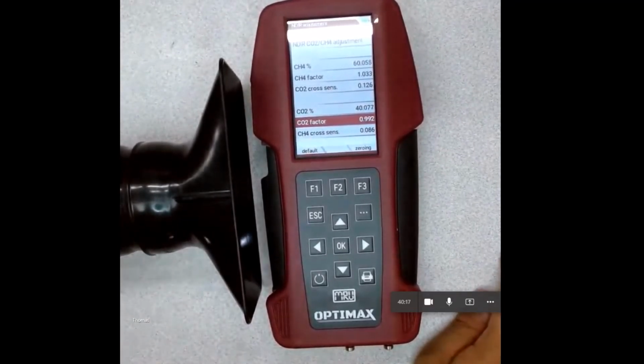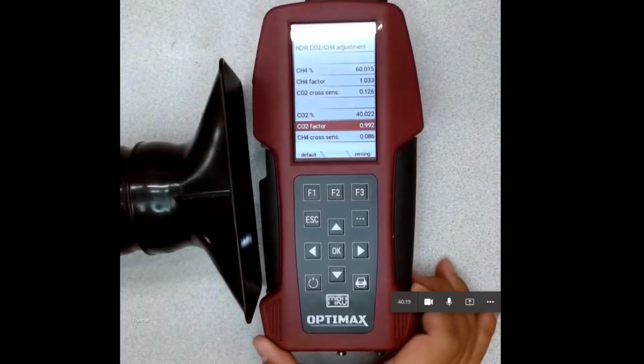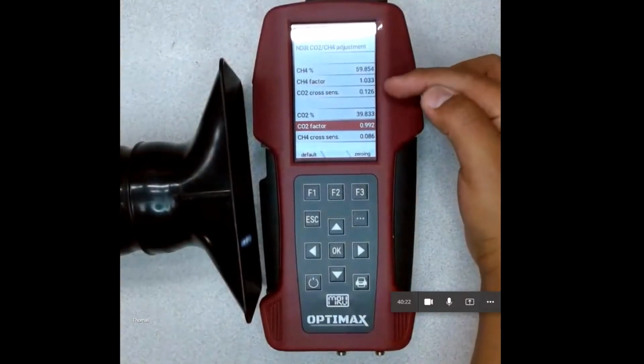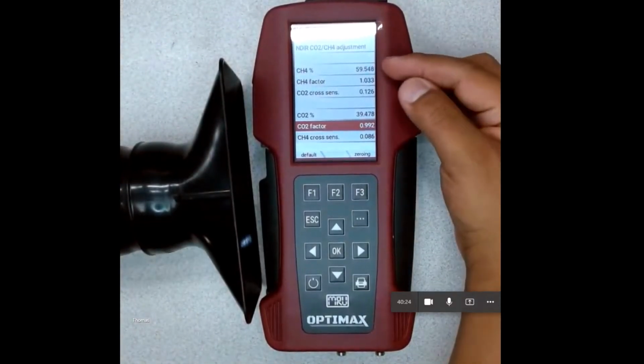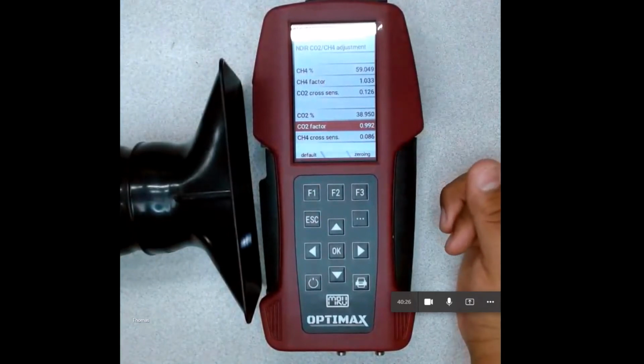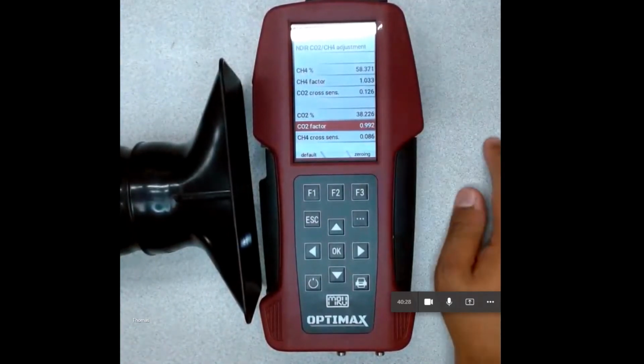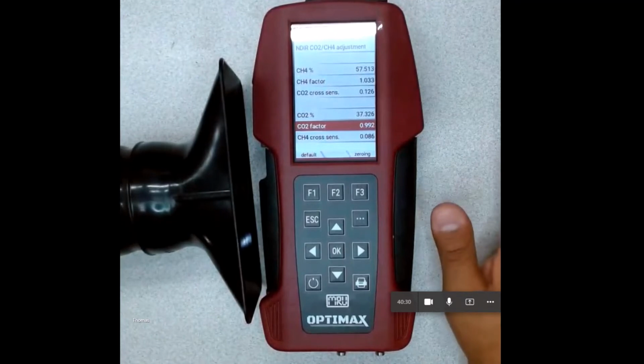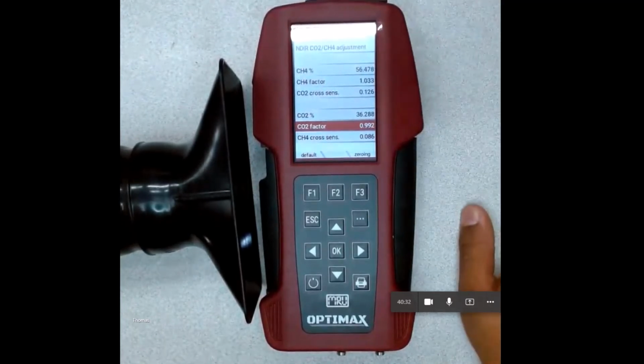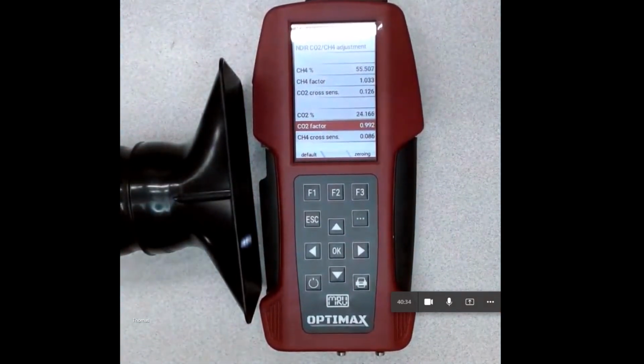And then one thing that we want to look for is we want to see the values from the gas, especially on the infrared. We want to see them come down really quick. The infrared is really responsive, and so as soon as it starts seeing fresh air, it should come down really quick. So probably within a minute, it should be near 0%.